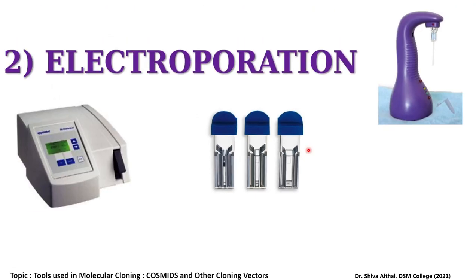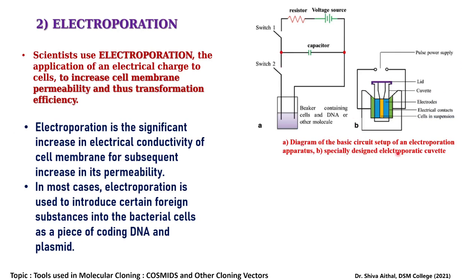The three cuvettes have different sample volumes: a large sample volume cuvette, a small cuvette, and a still smaller cuvette, though the outside dimensions are the same while the inside is engineered to hold different amounts of liquid. Inside the cuvette, you pour the sample containing bacteria and the gene of interest or plasmid to be inserted. On either side of the walls there are two electrodes; once placed inside the instrument they will be automatically attached to the positive and negative terminals and a continuous supply of electric current is ensured.